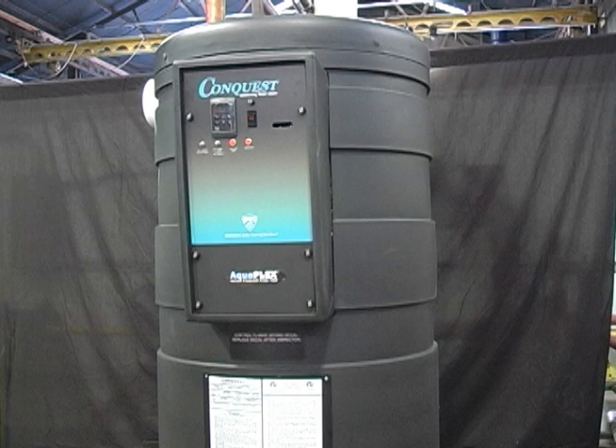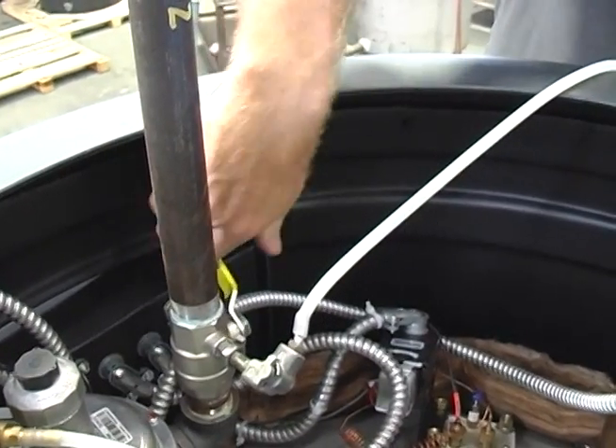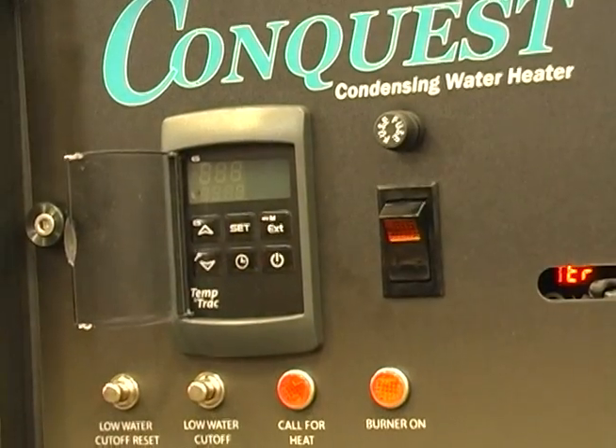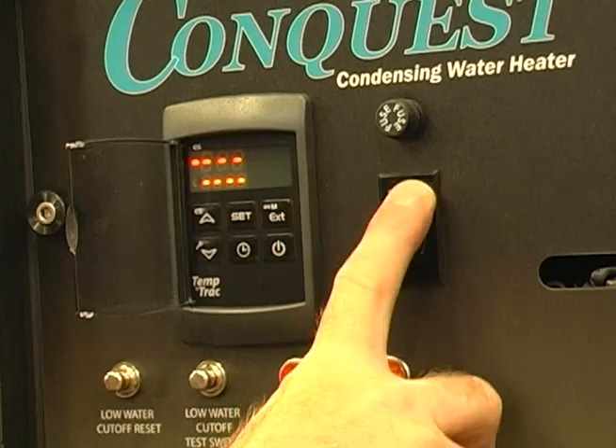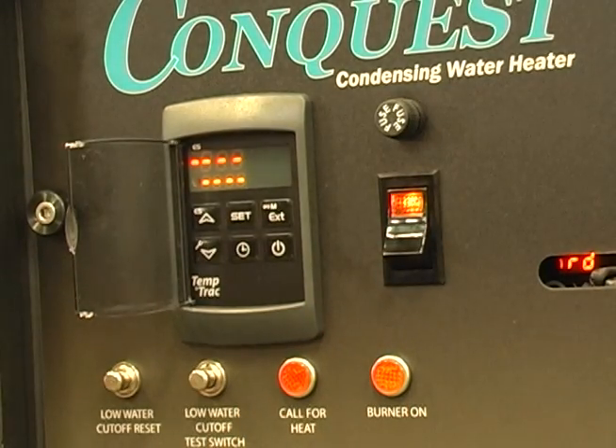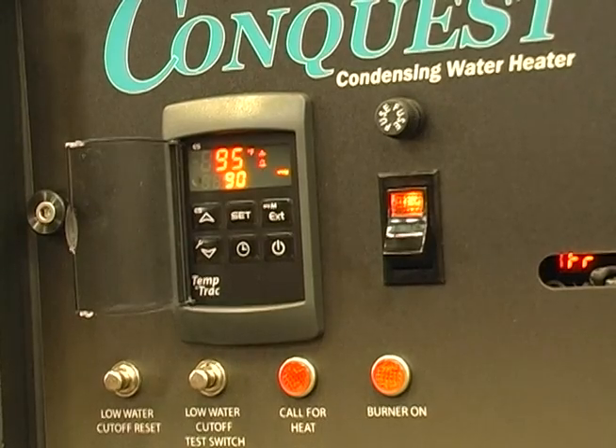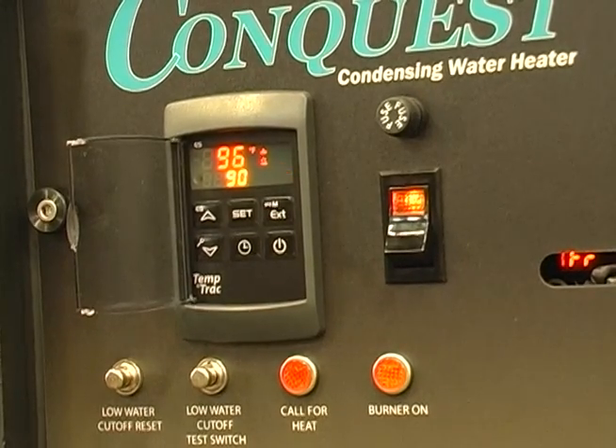To set up combustion on a 399,000 BTU on-off unit, begin by opening the main gas valve at the water heater. Move the rocker switch to the on position. This will initiate a trial for ignition. When the burner ignites, the burner on panel light will illuminate.